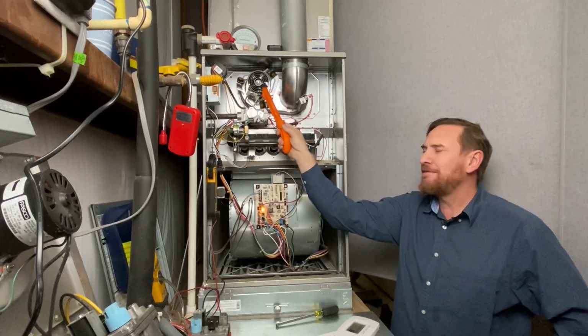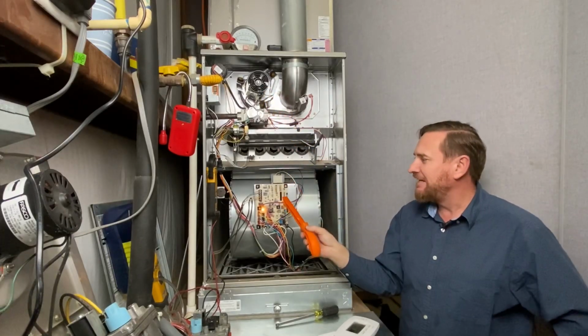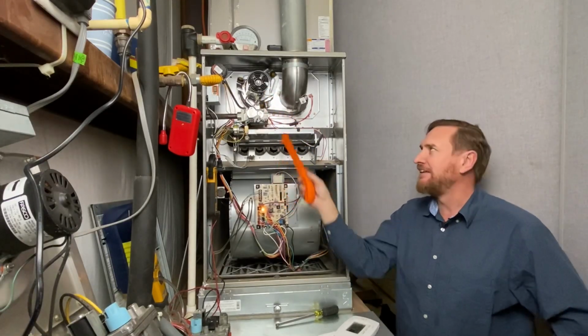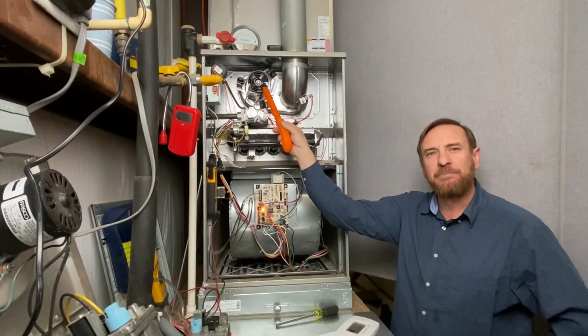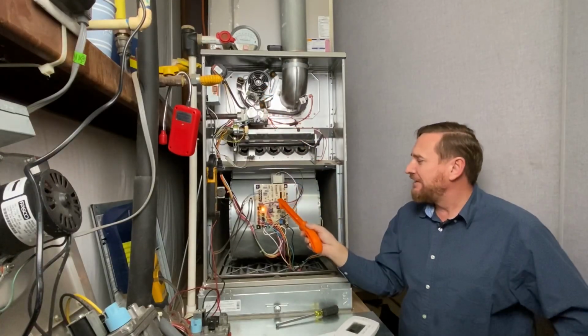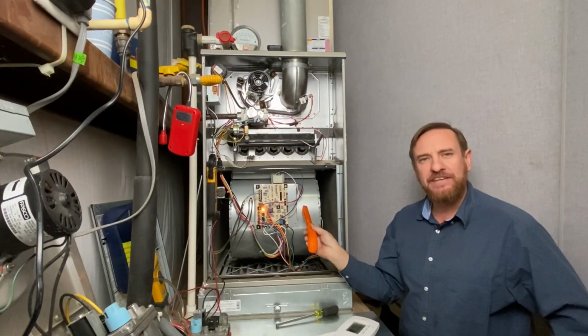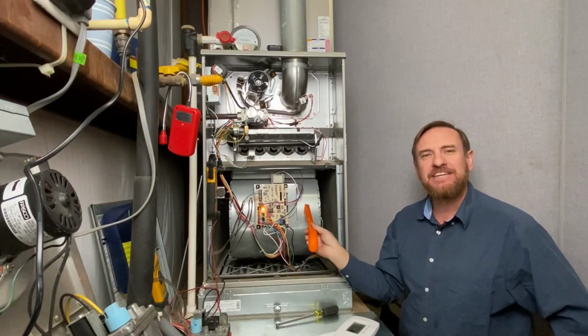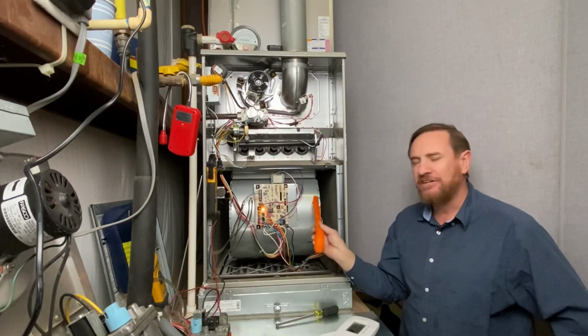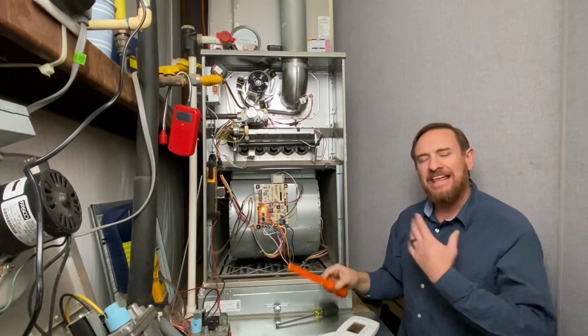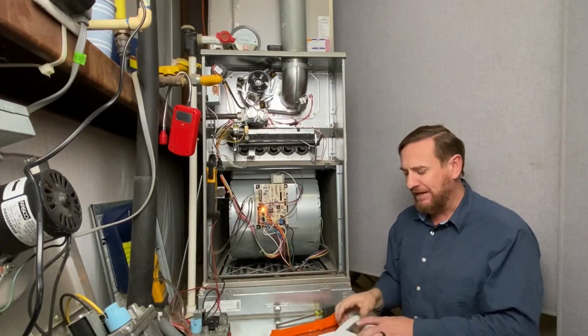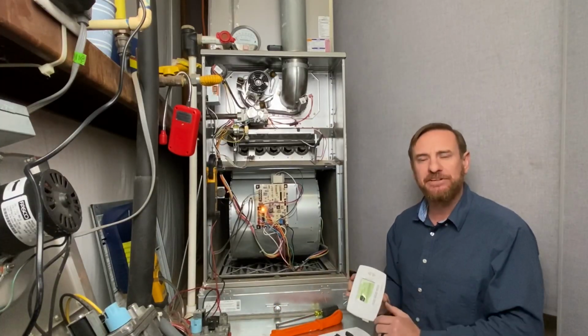The inducer fan motor stays running. The IFC lets it run for approximately 30 seconds and then shuts it off. This is called post-purge. The IFC lets the blower run to cool off the heat exchanger and get that efficiency of the heat back into the house. Then the IFC shuts off the blower motor. That's the sequence very quickly. But if we break it down, there's a lot of steps, a lot of very important steps in that.